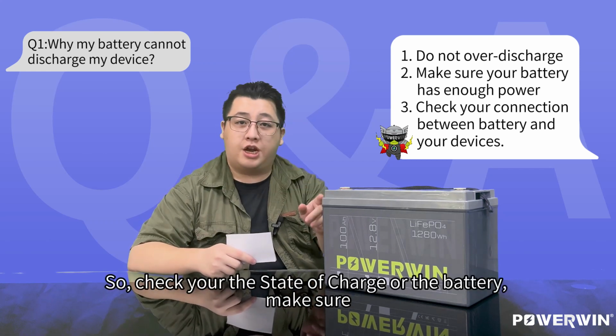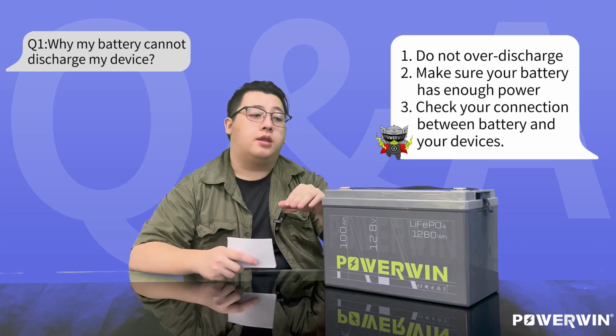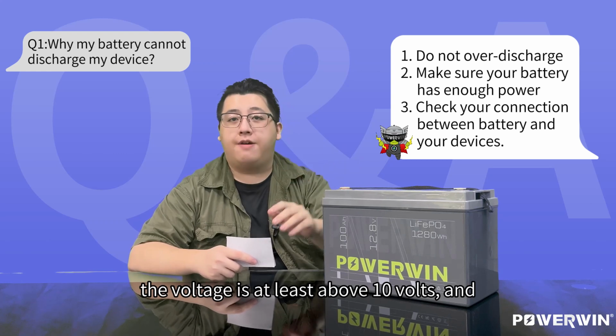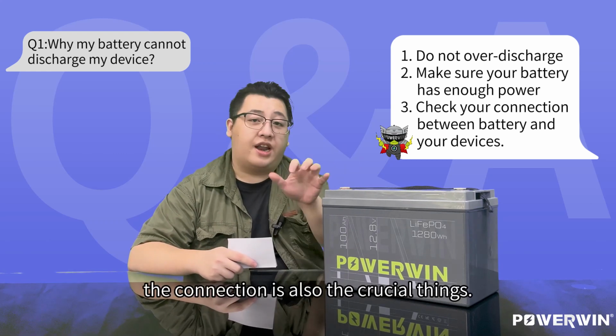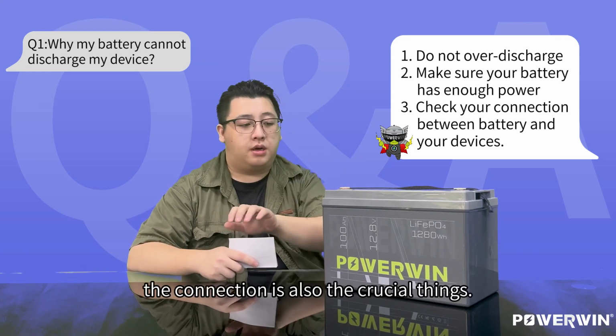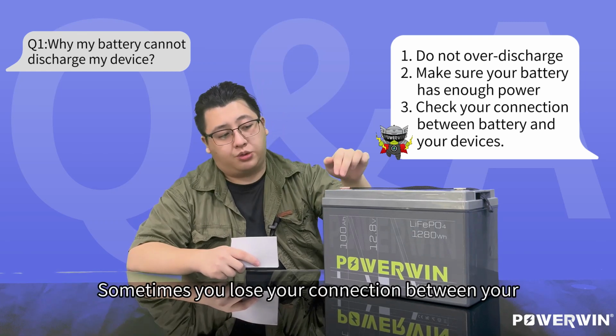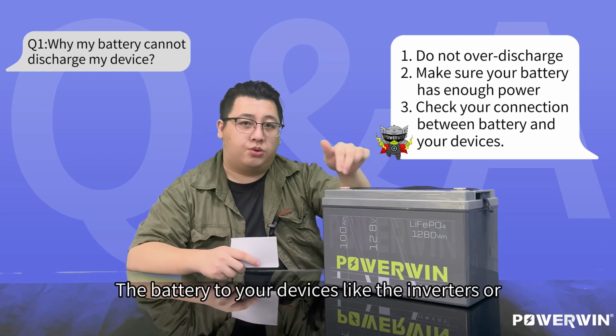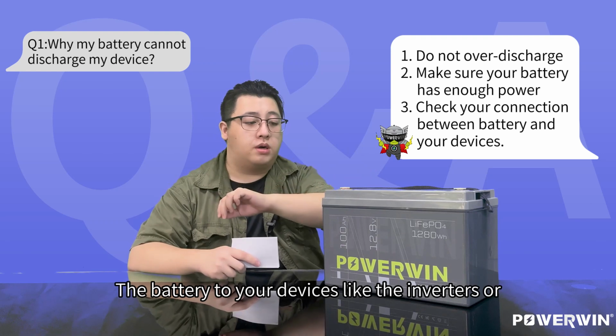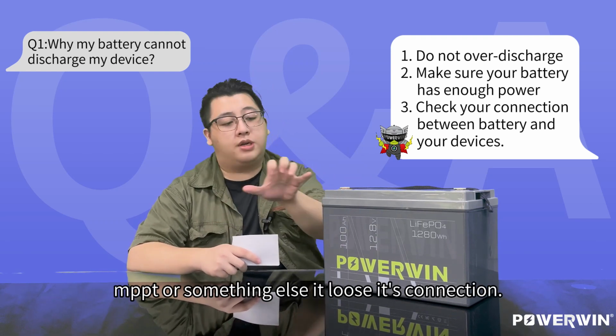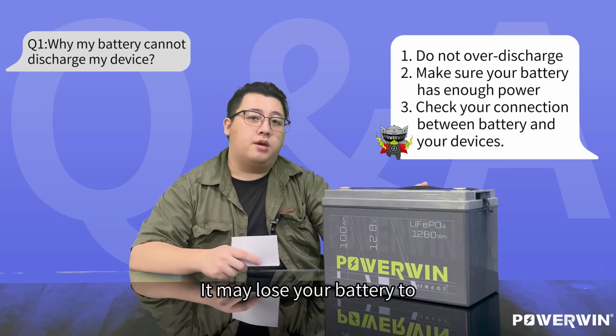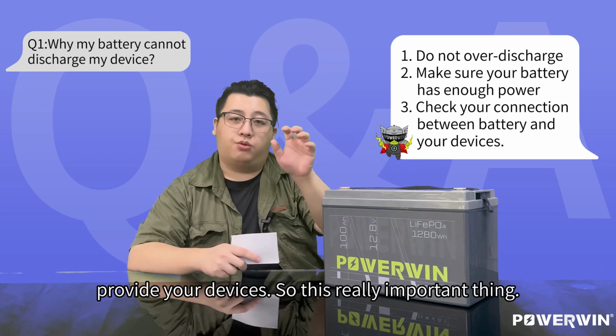So check the state of charge of the battery and make sure the voltage is at least above 10 volts. The connection is also crucial. Sometimes you lose connection between the battery and your devices, like inverters or MPPT controllers, and a loose connection may stop the battery from powering your devices. It's really important.